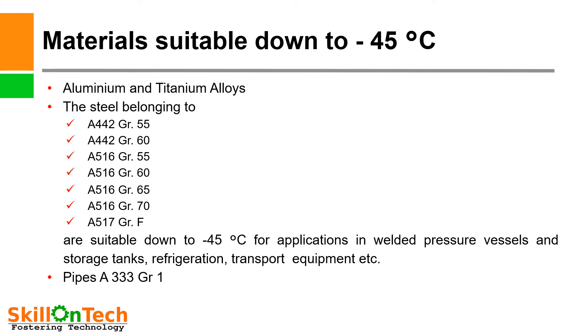Up to –45°C, the following materials can be used: aluminium and titanium alloys; steels belonging to A442 grade 55, A442 grade 60, A516 grade 55, A516 grade 60, A516 grade 65, and A516 grade 70 — these are carbon steel plates. A517 grade F is also suitable down to –45°C for applications in welded pressure vessels and storage tanks, refrigeration, and transport equipment.